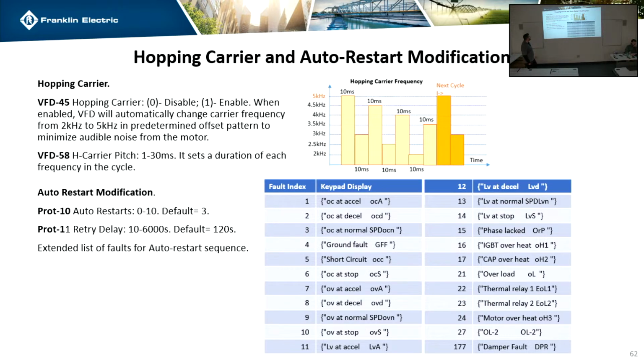This is going over the hopping carrier that we already went over. This is just how you would set it up. This is the auto restart setup for the drive. You would go into the protection settings. Number 10 is how many. The default is 3. Oh, and I was wrong. It's 120 seconds is the default. But you can range it all the way from 10 to 6,000 seconds.